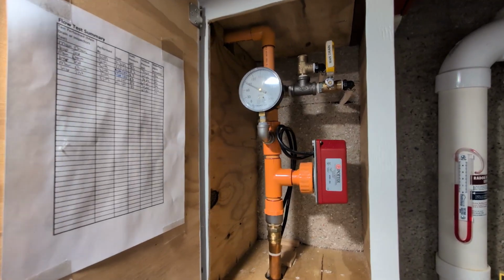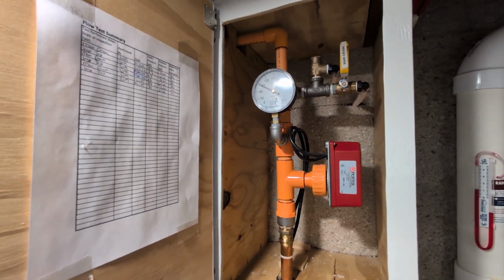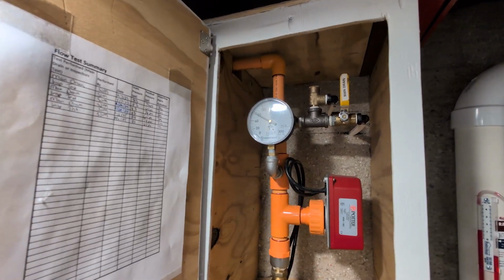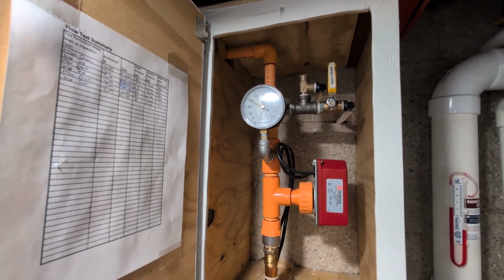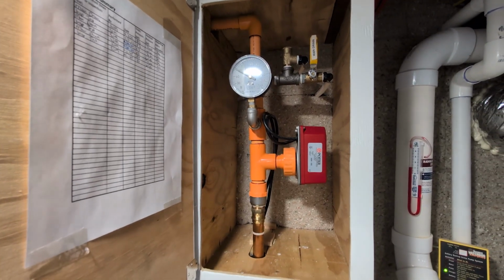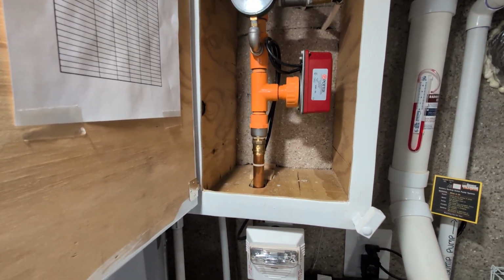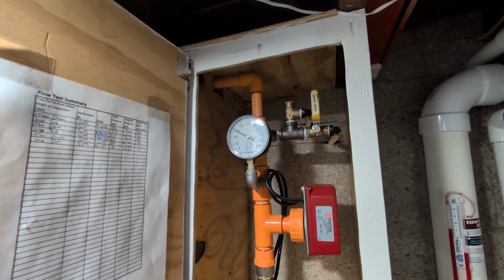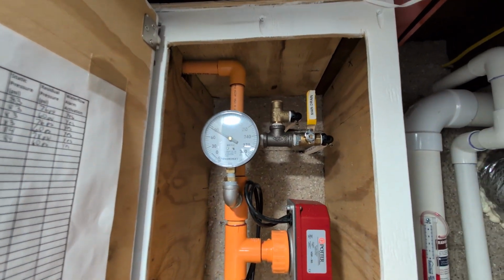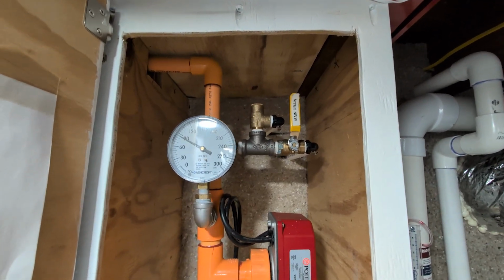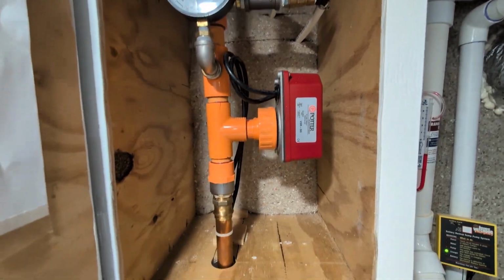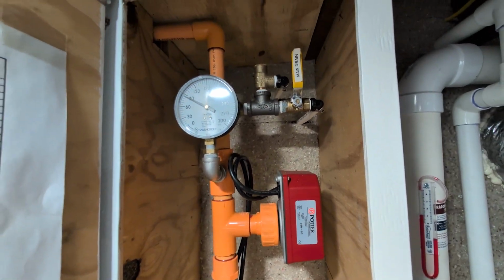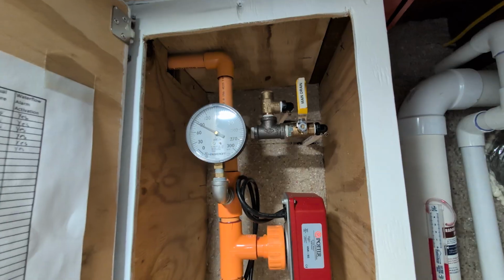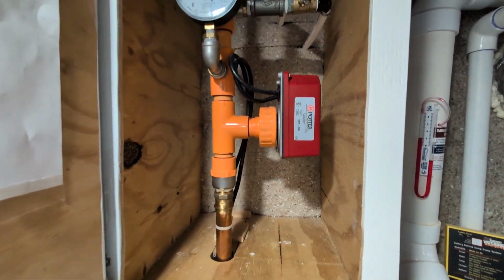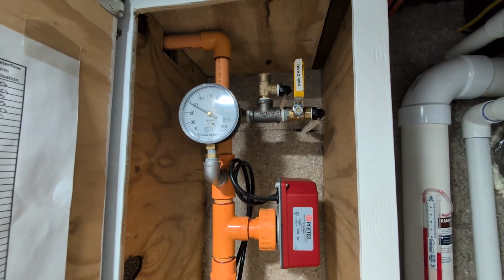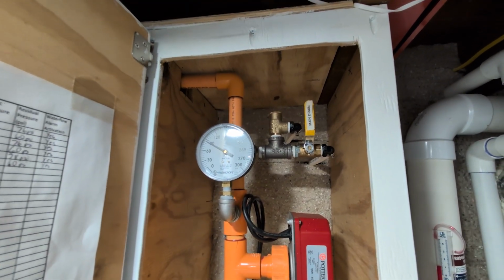And finally, many ask, well, do I need to have a contractor come in and do all the required inspection, testing, and maintenance per NFPA 25, which is the standard for the inspection, testing, and maintenance of water-based fire protection systems? The answer is no. NFPA 13D does not require you to follow NFPA 25 for the inspection, testing, and maintenance of water-based systems. Instead, it simply says that the installer, so the contractor, needs to provide the owner with information needed to perform their own inspection, testing, and maintenance on these systems.